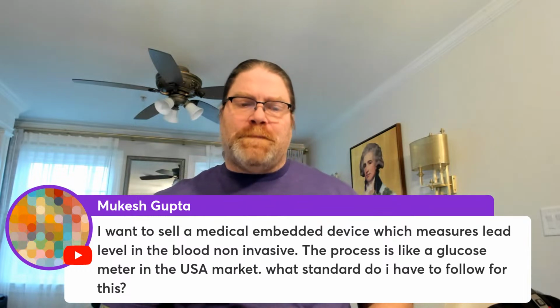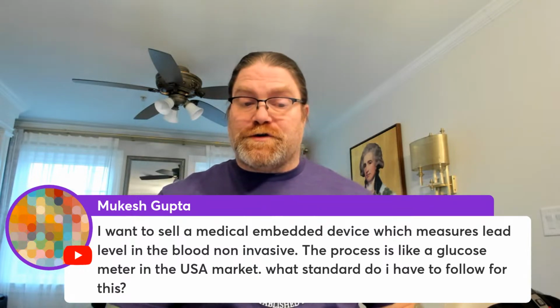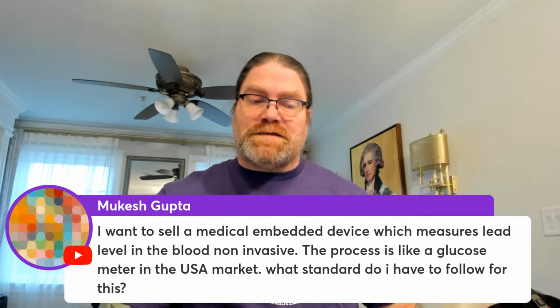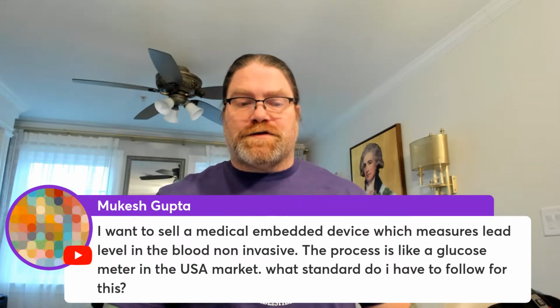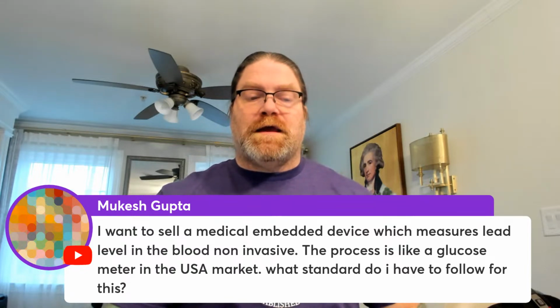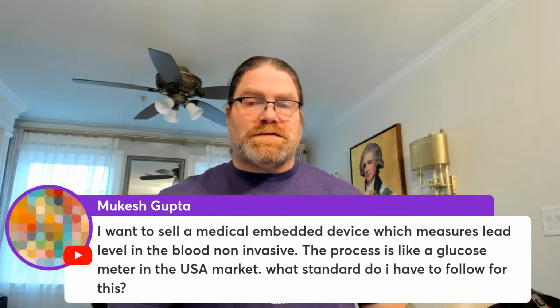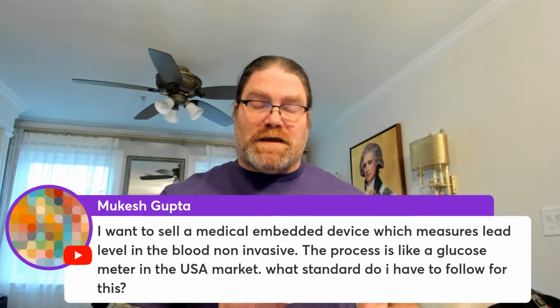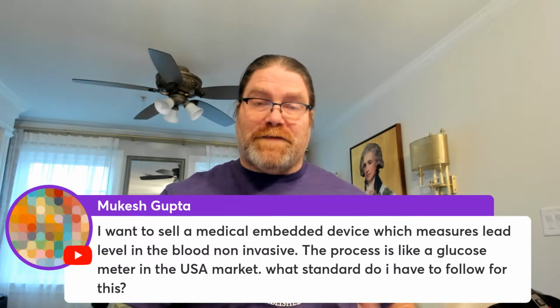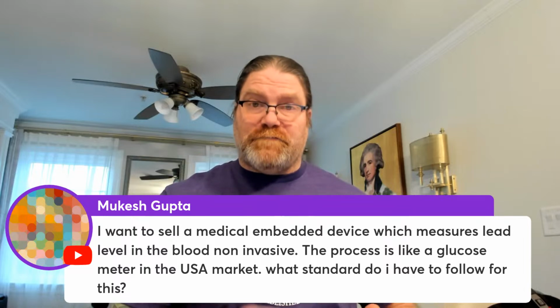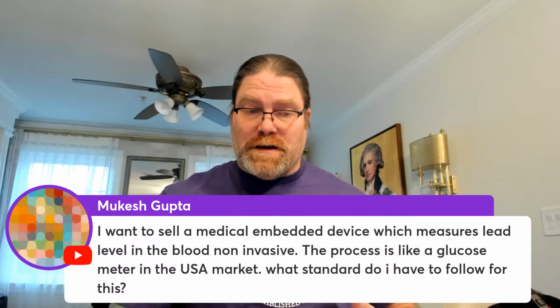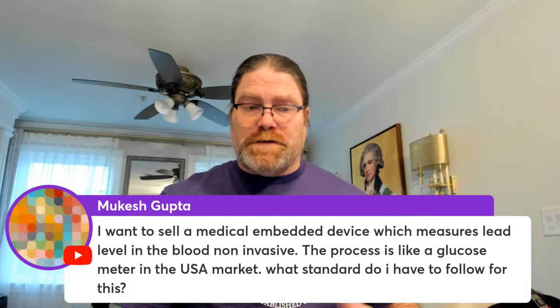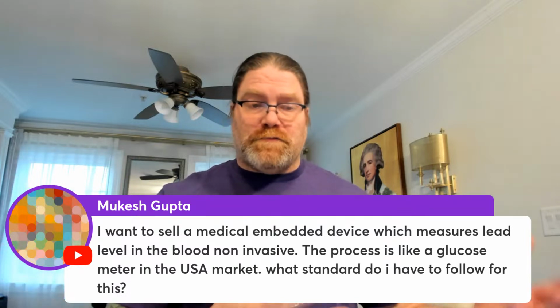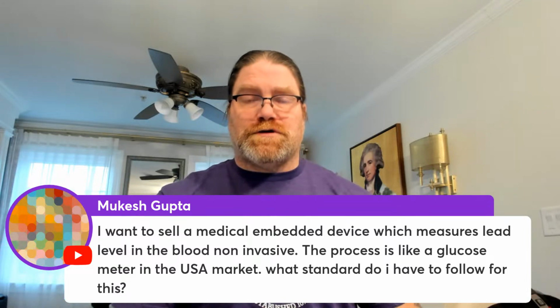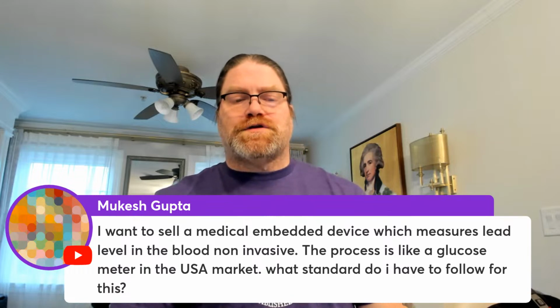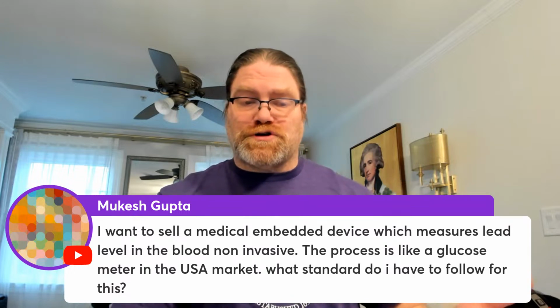So what's not clear from the description here is that they said it's non-invasive, but they also said it's like a glucose meter in the US. A glucose meter in the US is actually taking finger pricks. So it's an IVD device. It is invasive because you use a lancet and you get a drop of blood, but it's from capillary blood and it's done in vitro, not in real time on the patient. You're using a specimen, a drop of blood.